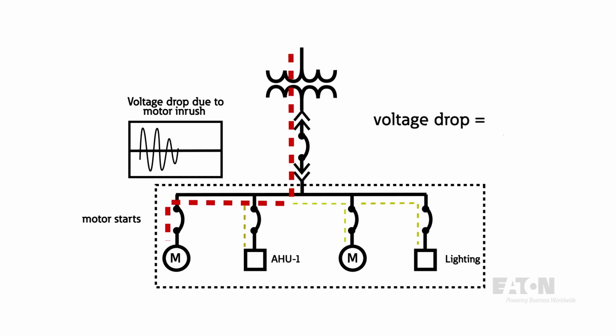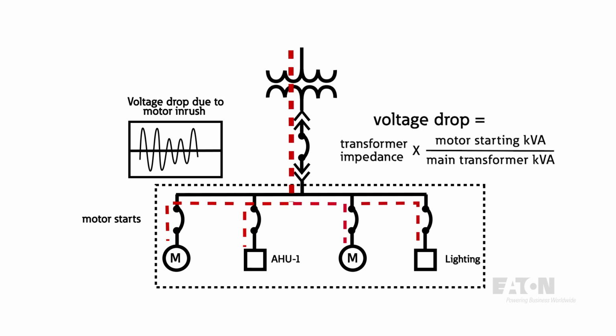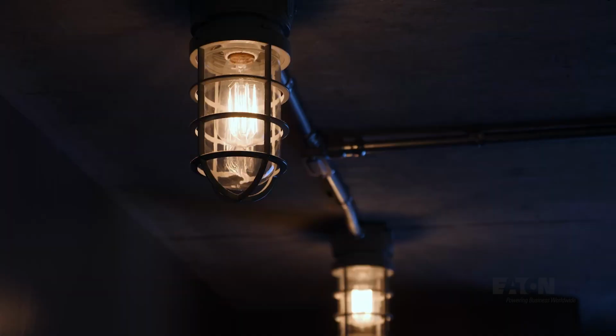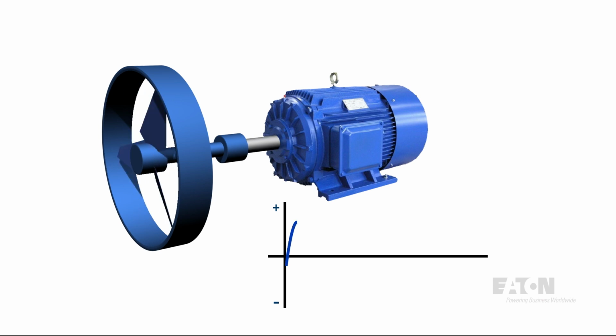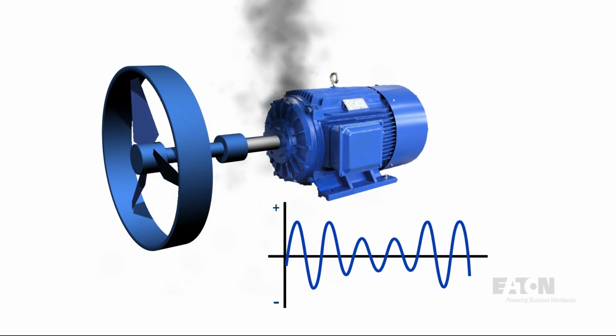The size of the motor and the impedance, or resistance to current flow, of the system dictate how much the voltage will drop. Consequently, voltage drops can lead to simple issues like light flicker, or more complicated and problematic situations like critical equipment shutting down. Depending on the problem and the cost or circumstances associated with the voltage issues, various motor starting techniques are used to avoid issues and prevent downtime or other situations.